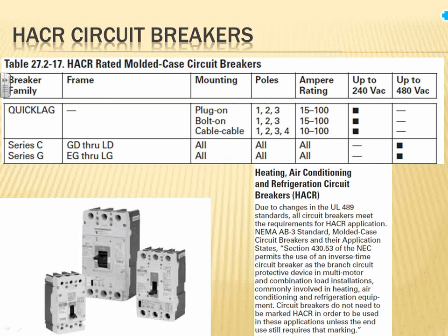Do you use fuses, or we always use HACR breakers if it's a piece of HVAC equipment. So I'll forward this one from Cutler Hammer directly from their website. And I went to Square D, the same thing, because it bothered me for a while. They say if they all meet UL 489, it meets the HACR requirement. Though, because the NEC code book keeps talking about the HACR, certain customers like to see that HACR on the circuit breaker, so they will label it for you if you request it.